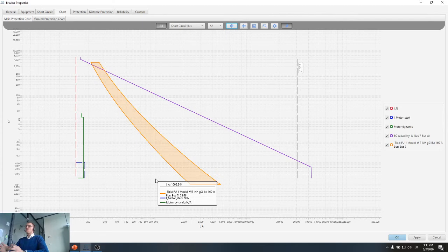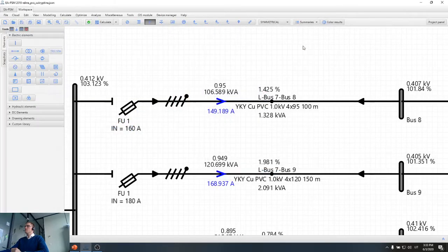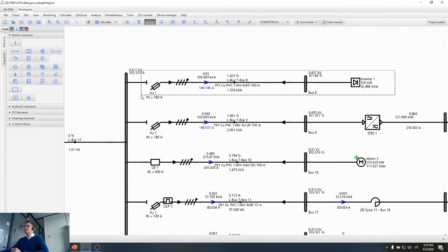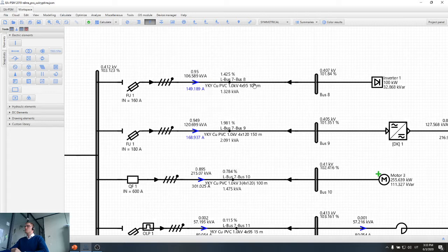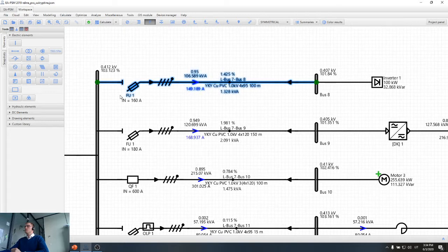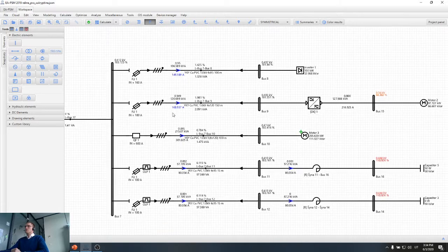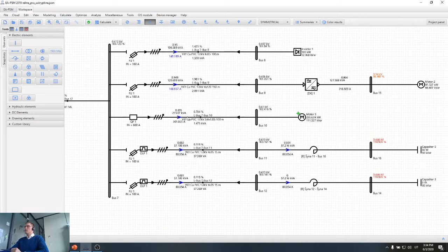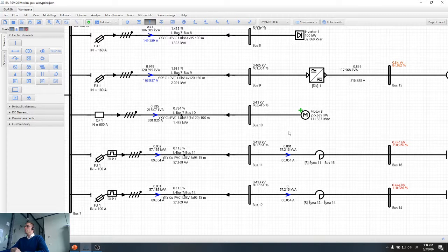First, we need to check whether our protection devices are capable to protect our equipment. So in case of the inverter, the only protection we need is actually the protection for the cable connecting the inverter with the network, and the cheapest way to do that is to use a simple fuse. Now let's go to other devices. So let's take motor.